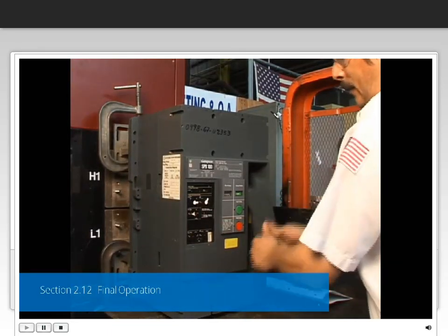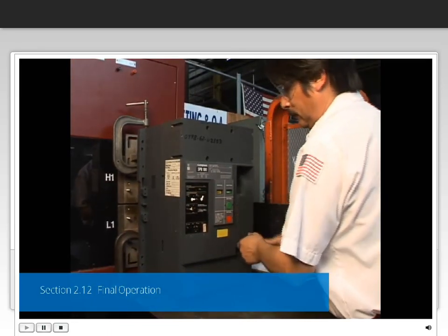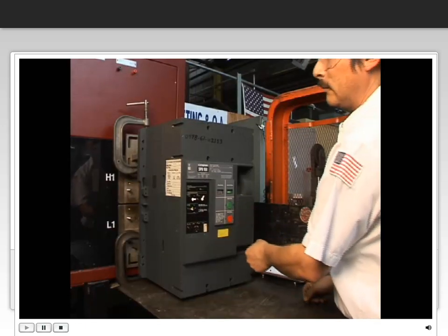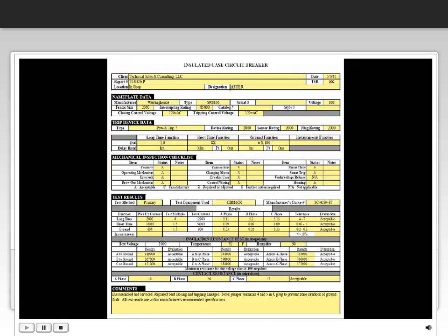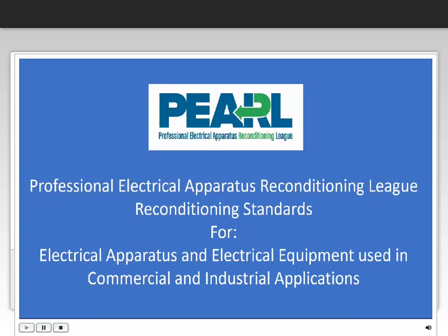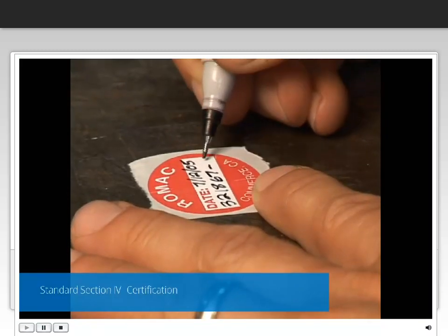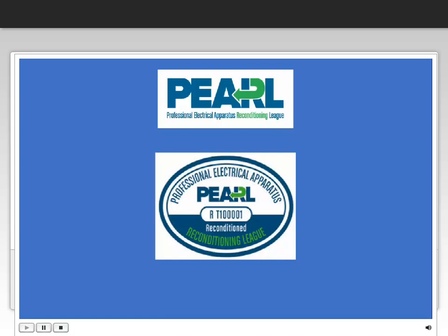A final manual and electrical operation test should be performed. The standard calls for this to be done 10 times. All results are recorded onto the test forms and into a database. If you refer to the Pearl Standards section, you will see that considerably more time must be devoted than what is displayed in this video to properly perform the reconditioning process. Considerable care should be taken to ensure that all applicable steps are followed. Only when all steps and inspections are performed will the breaker receive this Romac Breaker Quality Seal, as well as the Pearl Quality Seal.